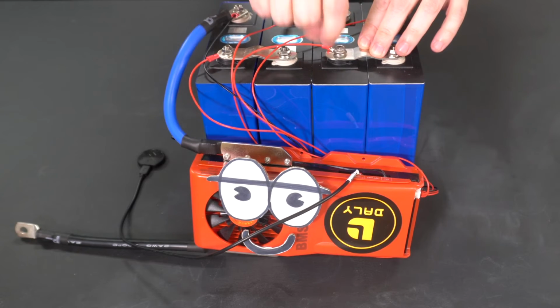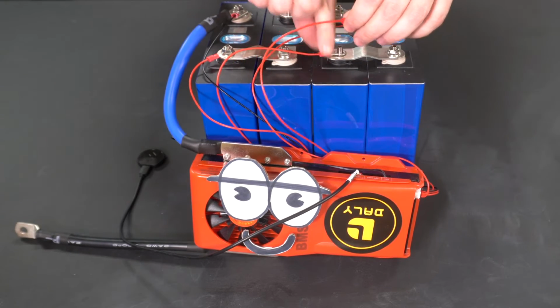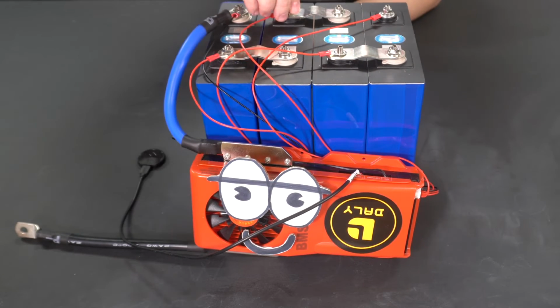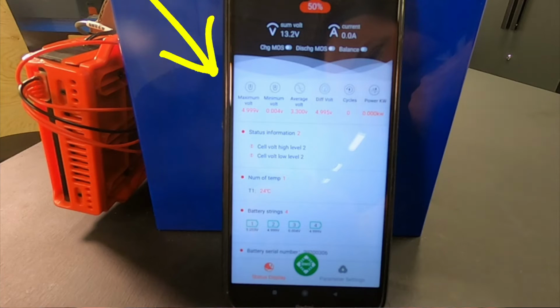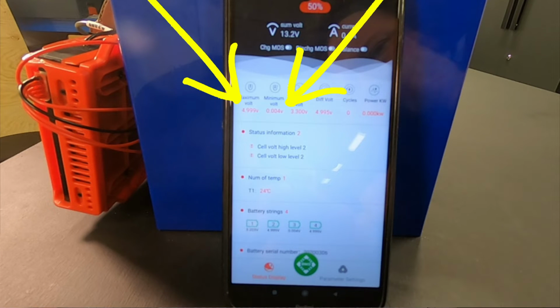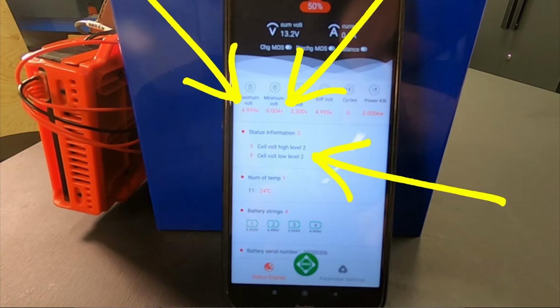To demonstrate a faulty wiring, I'm going to switch 2 of the balance leads so we can see how the BMS reacts. As you can see, we get some funky voltages. When we switch the balance leads, the BMS no longer measures the cell voltages correctly, which has triggered it to go into a fault mode.